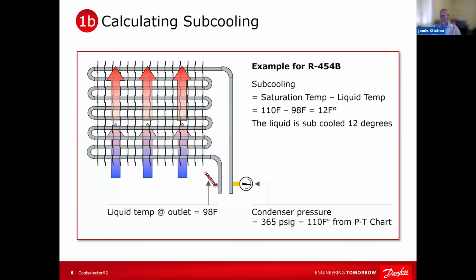And some of your liquid flashes to vapor, and I'm not going to go into the details why, but it's pretty much locking up the excess energy that's in the liquid. That's what creates your vapor. Coming out of your compressor, you don't have liquid. If you do, you've got bigger problems. Trust me on this one. So you've got dry superheated vapor coming out of your compressor.